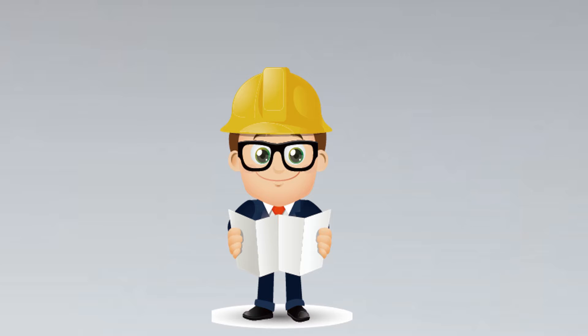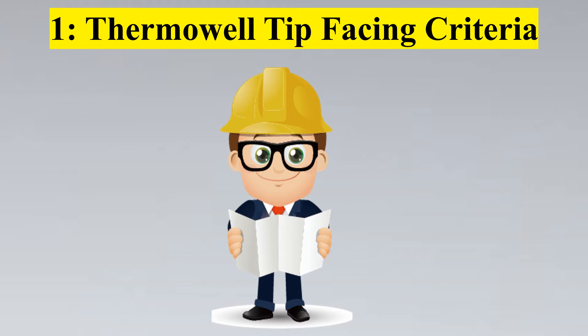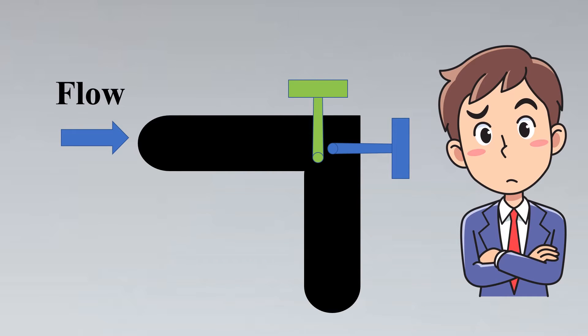Let us look into the first criteria which is the most important criteria, thermowell tip facing criteria. What does this criteria state? It states that for example, this is your pipe and this is an elbow. Now here is your flow direction. So how would you install your thermowell on this elbow? Should it be installed like this or should it be installed like this? Isn't this a bit confusing?